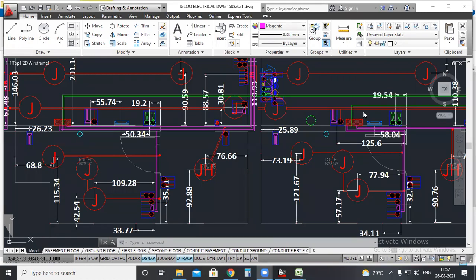Through the ground, you can take depending upon the conditions, depending on the floor height, or through the wall. Also, there is a limit. I think there is a limit for the wall also, 25 mm, 32 mm. I don't think you can take 32 mm conduit through a 20 centimeter width. Depending upon the width of the wall, you can take the plastering width.